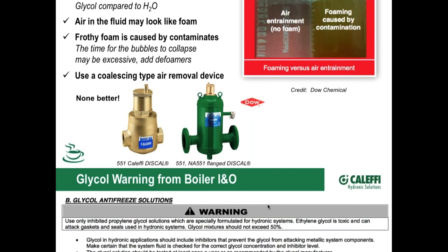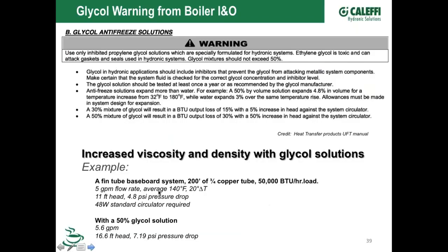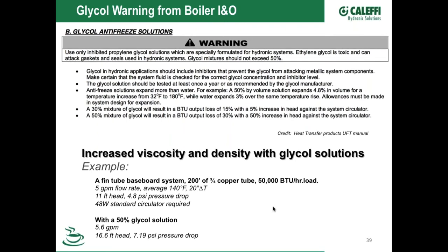I'm running out of time, but this shows an example of a basic residential system that had water in it, and the customer called saying they're going to Florida this winter and want the hydronic system winterized so it doesn't freeze. If you took the water out of this system with a five gallon per minute flow rate and a 46-48 watt pump, putting in a 50% glycol solution is going to take quite a bit more pumping power to move that fluid because of its viscosity. So if you're changing fluid, make sure you adjust your pumping power accordingly.